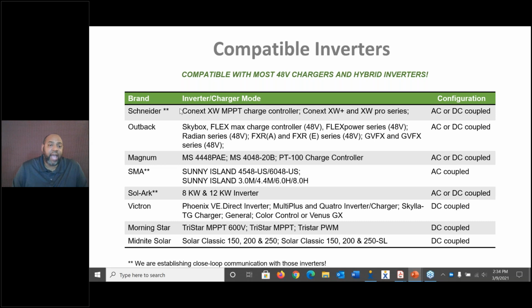And if you notice these asterisks right here, these asterisks just indicate that we have closed loop communication with some of these inverters. Right now, it's the Schneider and the Sol-Ark, and we are working on the SMA. If you look to the right of this column, you will notice that our batteries can be AC coupled or DC coupled depending on the inverter.